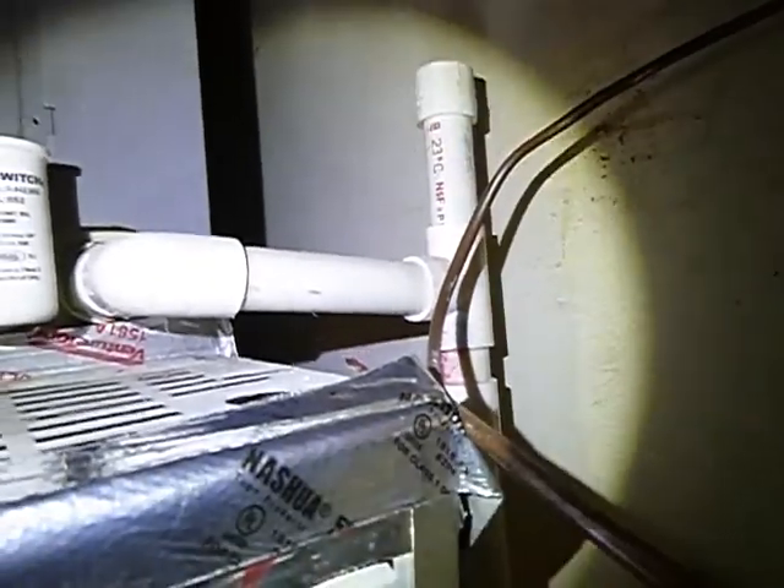We have a safety switch — I call them a float switch. The primary evaporator drain line does not have a P-trap, and it's not insulated.